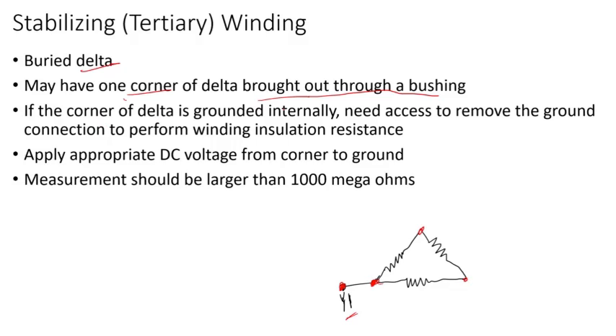If the corner of the delta is grounded internally, you need access to remove the ground connection. If you have a bushing, all you need to do is remove this jumper, conductor, or bus bar. Now you have the bushing isolated - the delta is not connected to ground anymore.